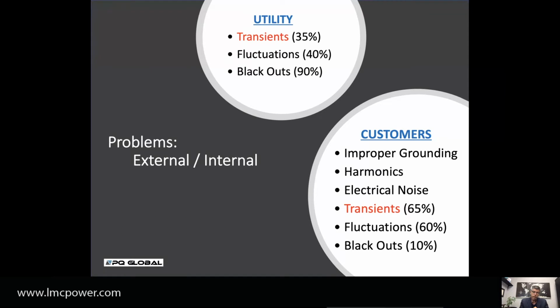So some of the customers that I have in areas where there's not a lot of lightning tend to give me the excuse of, well, I don't need it, there is no lightning around here. But what they need to see is that 65% of the problems are actually generated by their own building. If it's a factory, they have equipment that starts and turns off all day long. So unless the factory is turned off, there are transients.